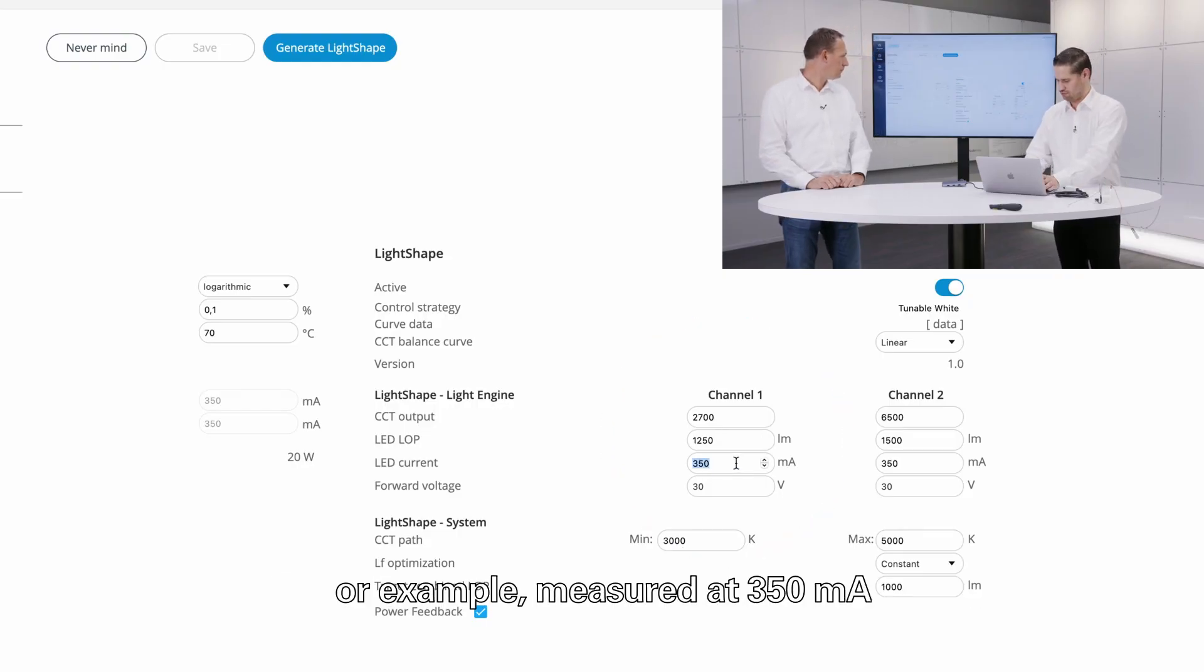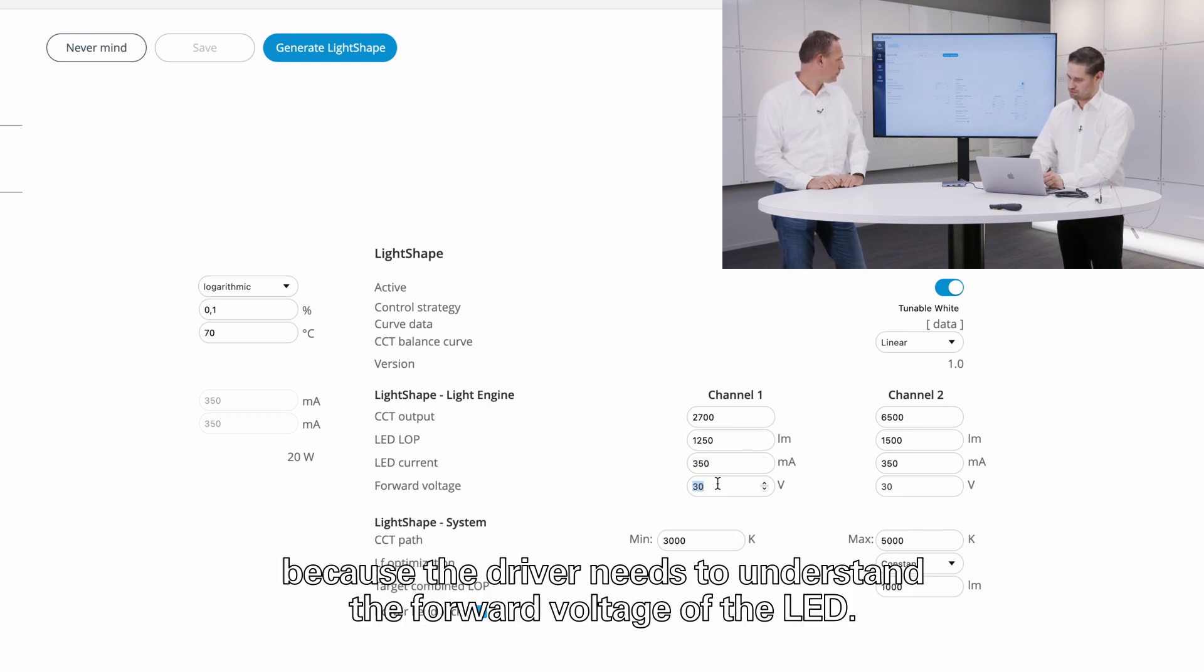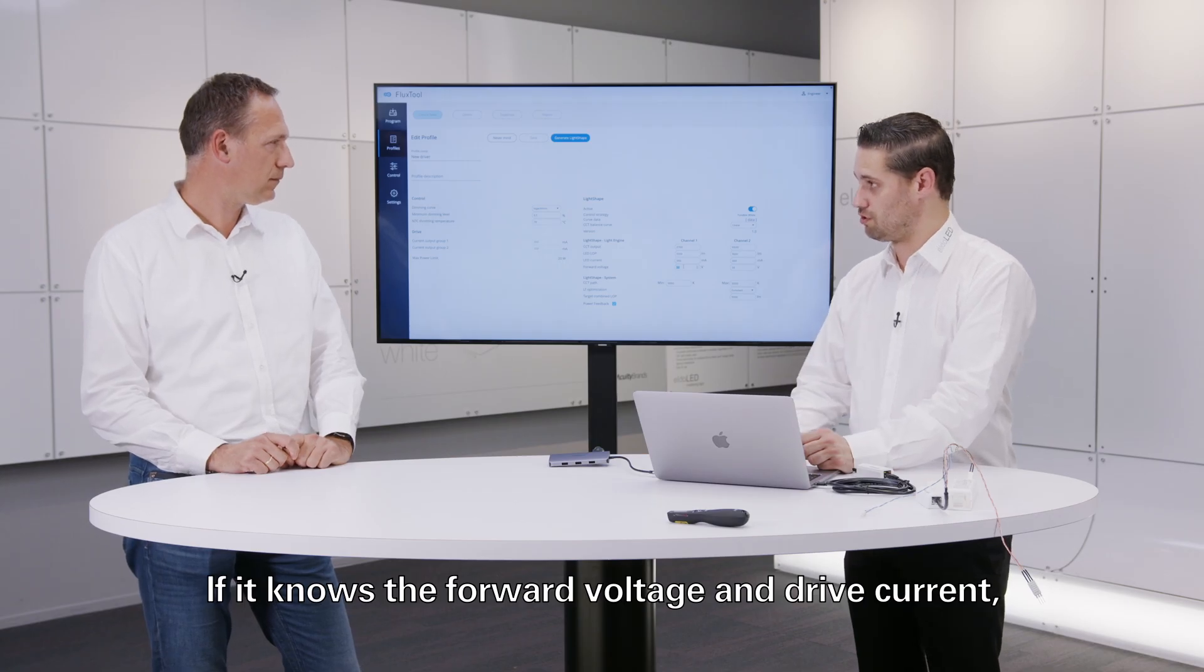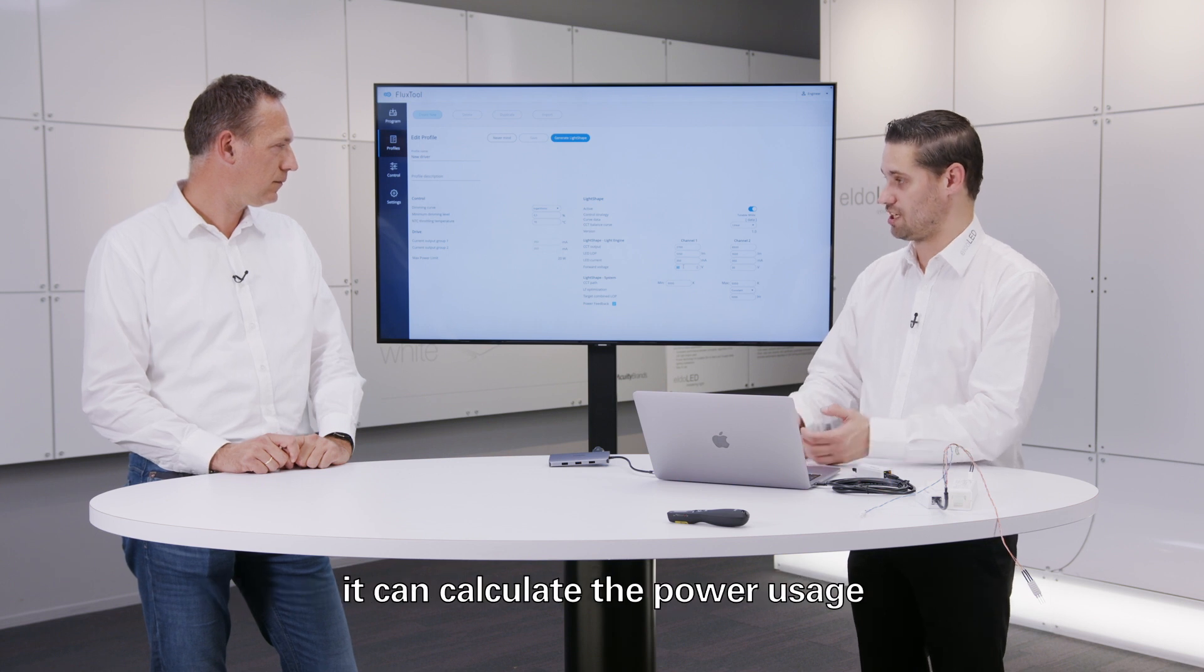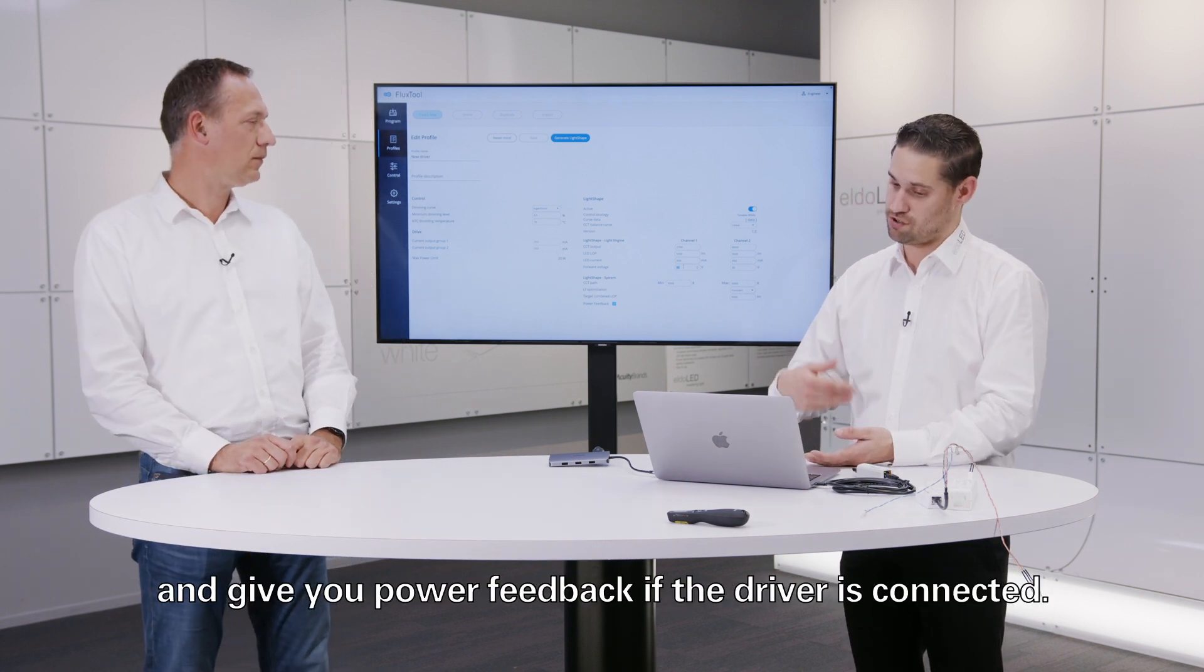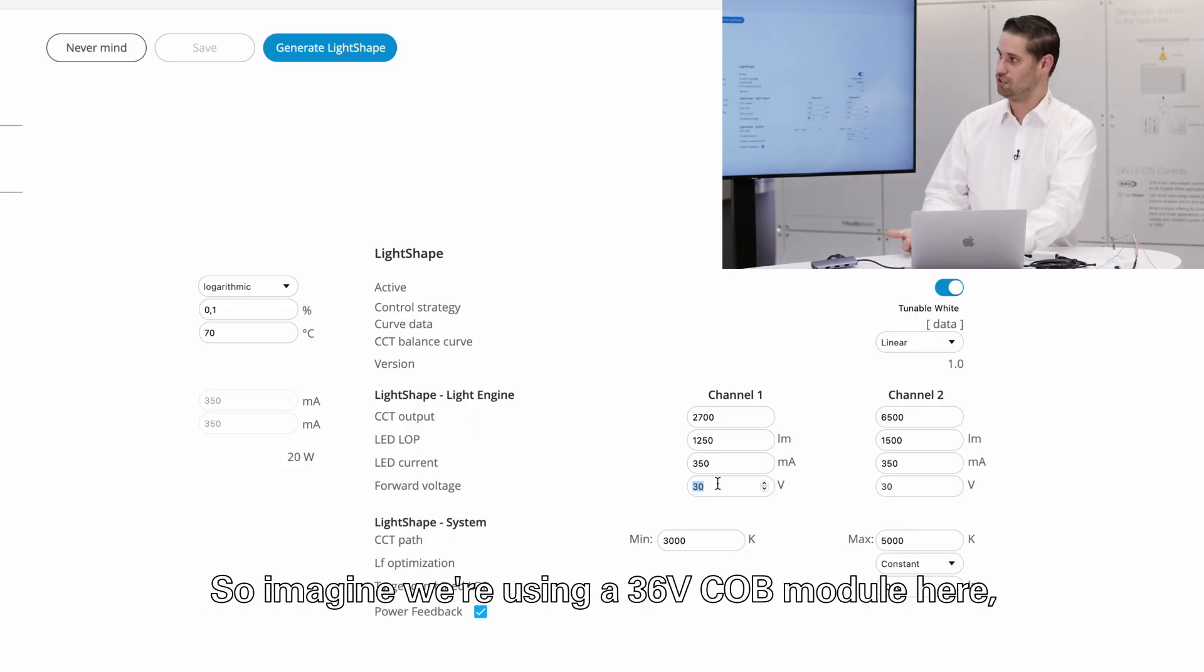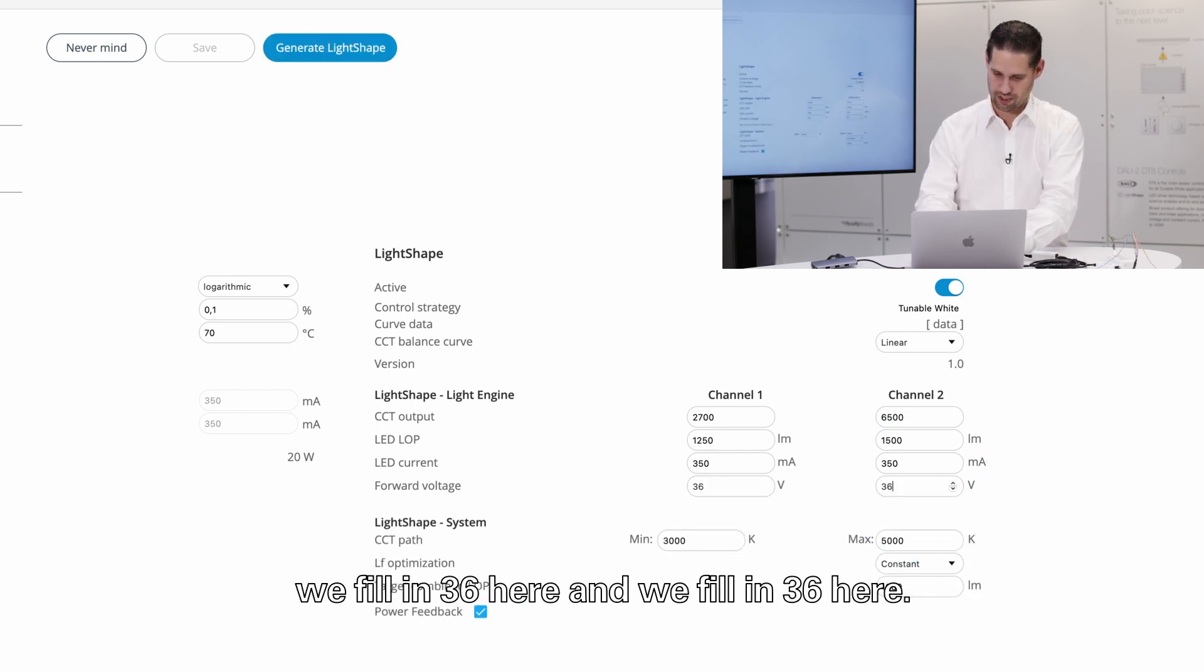And you can also fill in the forward voltage, because the driver needs to understand the forward voltage of the LED. If it knows the forward voltage and the drive current, it can also calculate the power usage and gives you power feedback if the driver is connected. So imagine we're using a 36 volt COB module here. We fill in 36 here, we're filling in 36 here. I'm setting the system again the same as we used to have before.